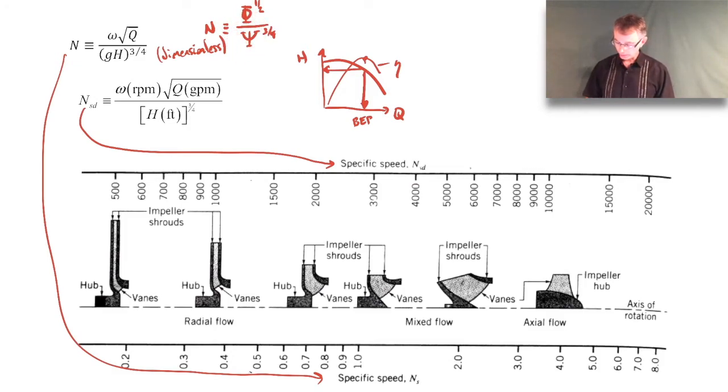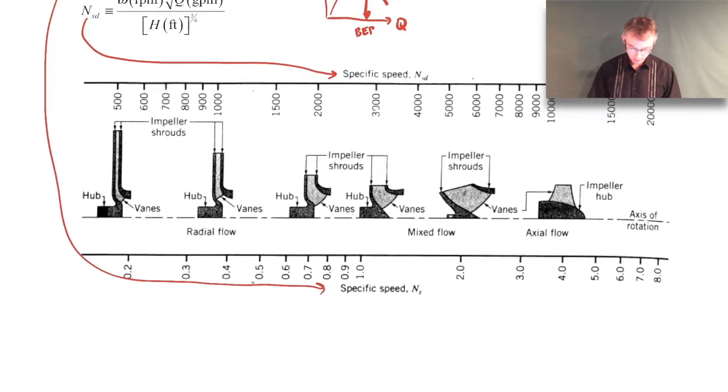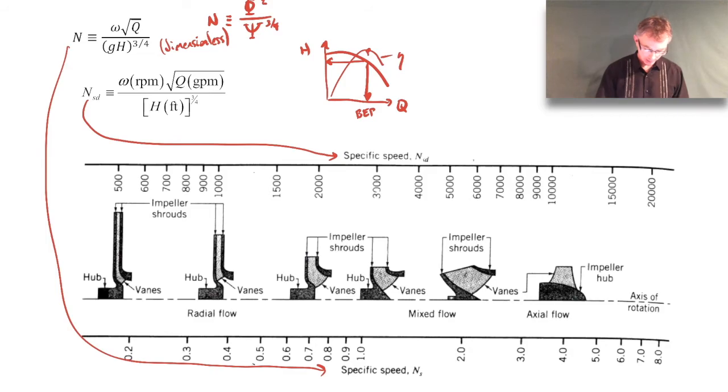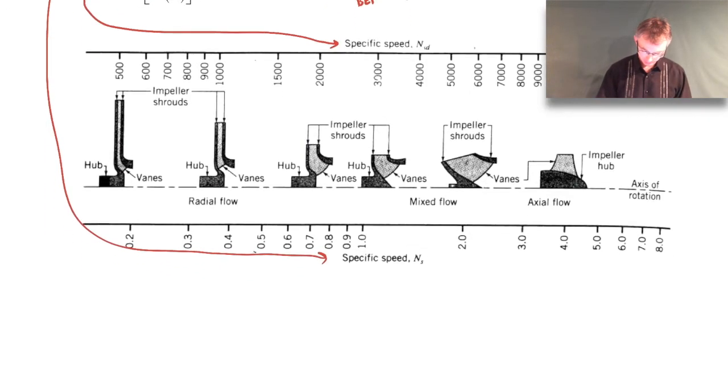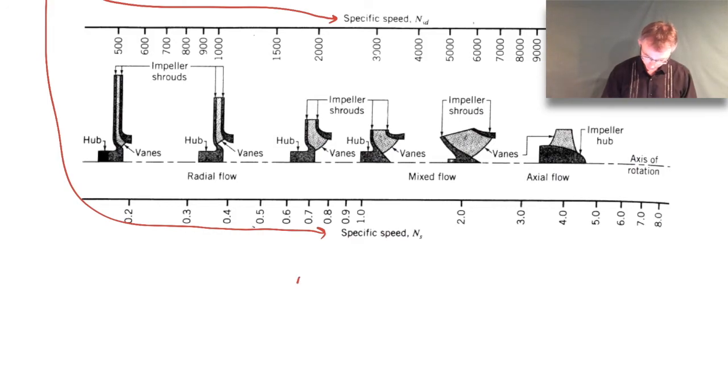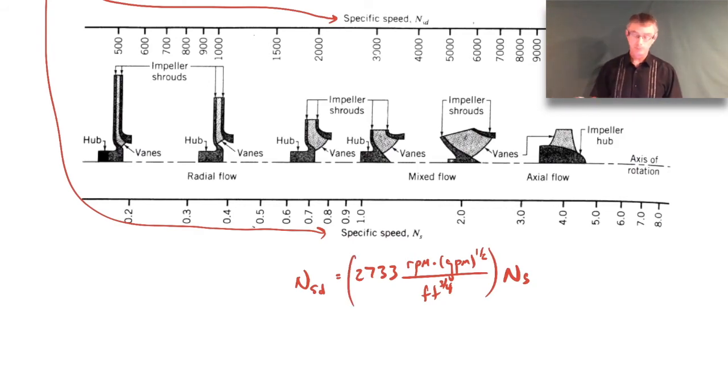So specific speed, again, just allows you to figure out what class of pump type is going to be most efficient for your given operation. All right, so let's see if there's any additional things I wanted to say. If you wanted to convert between the dimensionless and the dimensional specific speeds, the conversion is the following. So let's see here, the dimensional one is 2733 RPM gallons per minute square root all over feet to the three-fourths power times the dimensionless specific speed. So if you wanted to do that conversion, there it is.